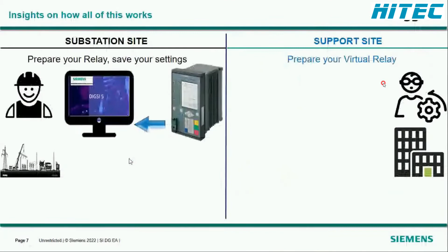Going into more detail: at the substation site, the engineer loads the special file, reads all the settings, and creates a special SIM file from DIGSI, which is sent to the support site, allowing the creation of an exact virtual replica of the relay. Same for the test set - we read all the test files, save them, and send them to the engineer who runs the tests against the virtual test set.